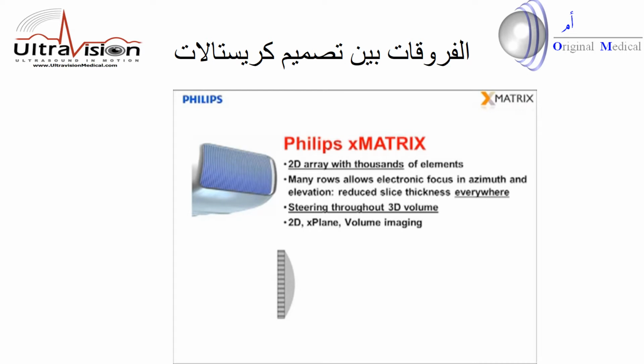In an X-matrix array, the elevation dimension is separated into elements in the same way that it is in azimuth with many rows. Having many rows with independent delay control provides the same degree of electronic control of the acoustic beam in elevation as there is in azimuth. We can focus the beam over a much larger focal length, resulting in good slice thickness everywhere. We can also use this electronic control of elevation to steer the acoustic beam throughout the entire three-dimensional field of view. This provides novel modes such as X-plane with two planes displayed simultaneously in real time, as well as 3D.